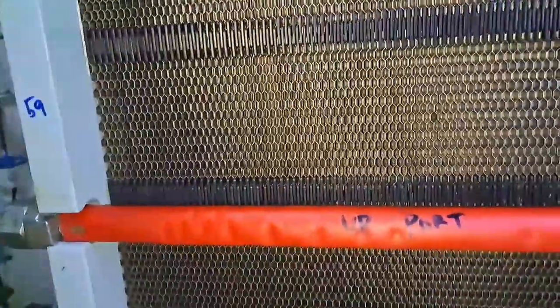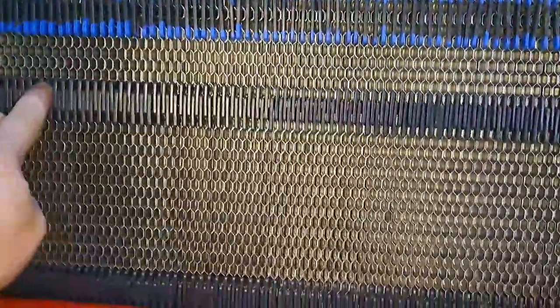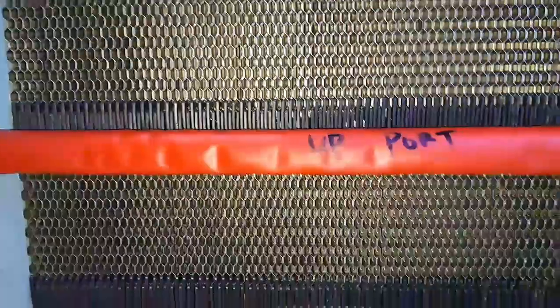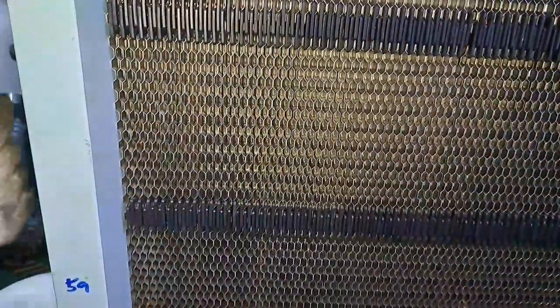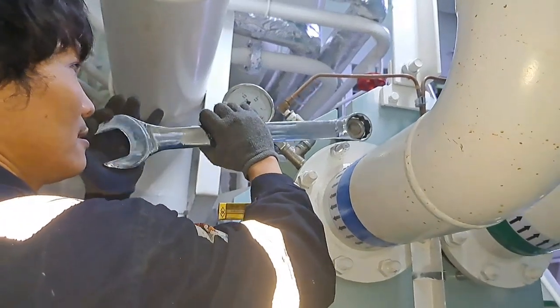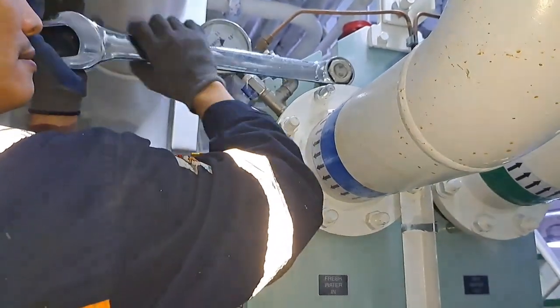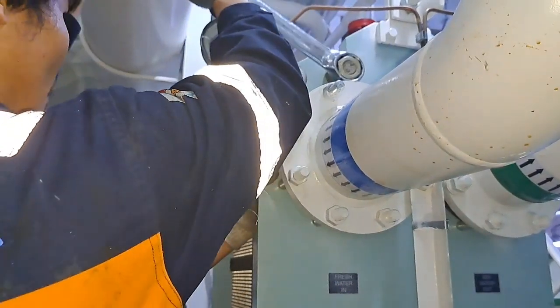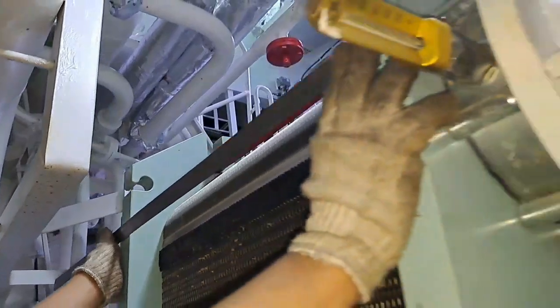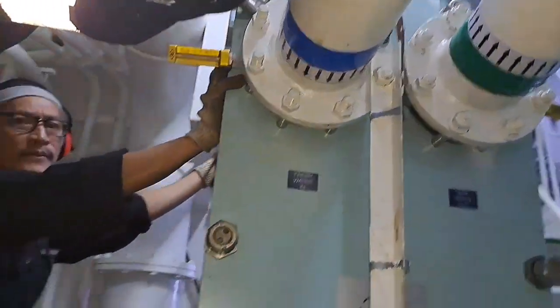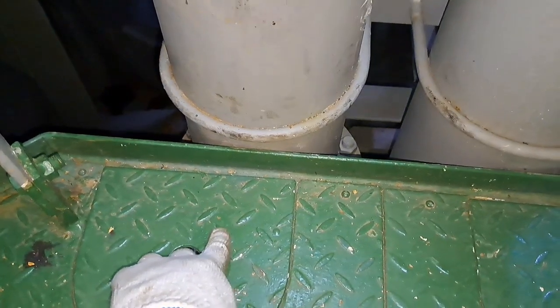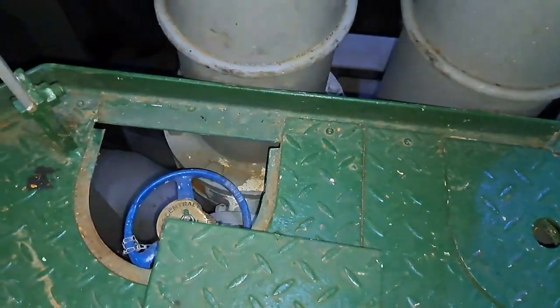The plate heat exchanger. You can perform this kind of maintenance at least once every 3 to 6 months. It depends upon the performance. As mentioned above, regular visual examinations are important. Make sure the plate pack is tightened to specification, the carrying and guide bars are lubricated, and the gaskets are free of wear and damage.